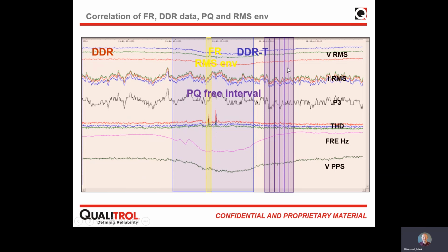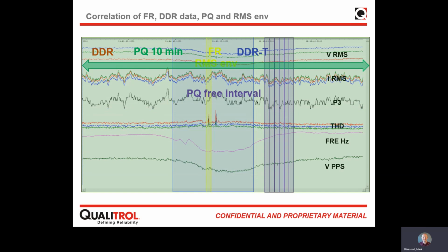And then the last one is this 10-minute sample that we talked about, which is required by the standard. So for every piece of this segment, we'd have one sample which shows the maximum and the minimum and the average of all of those calculated values.